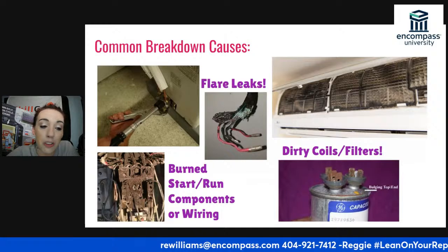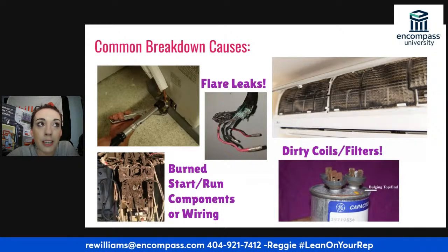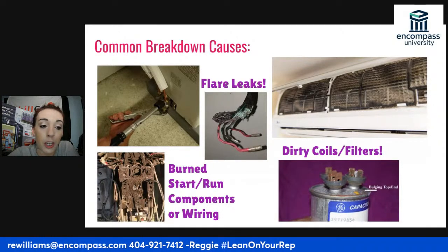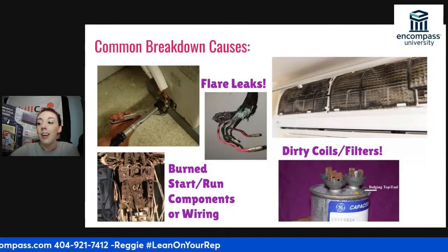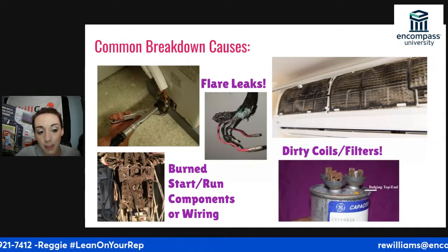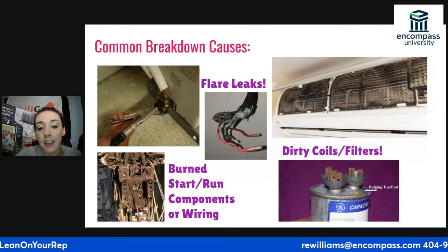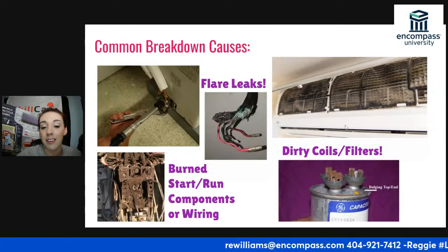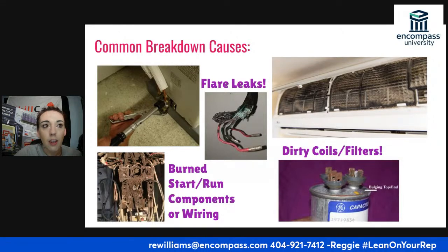And all you would have had to have done on maintenance is do a tug test. That customer is going to be very upset if you were just there for maintenance and then they have an arcing situation where it shorts out a bunch of components. You want to make sure that your butt is covered by doing that tug test. Super easy, takes 2 minutes, you guys. Never skip the tug test.